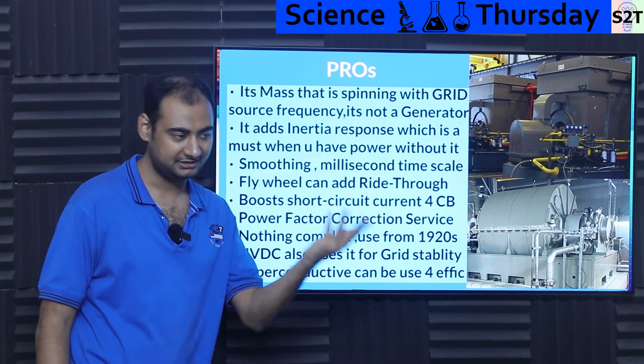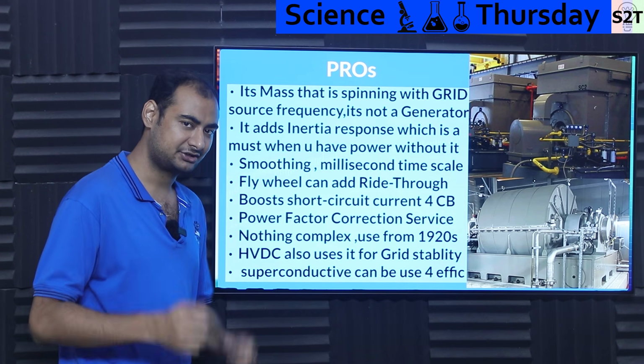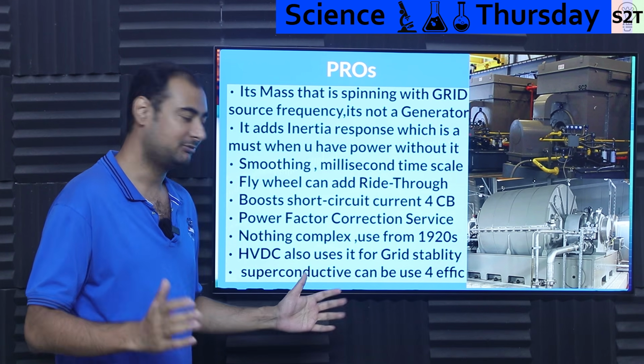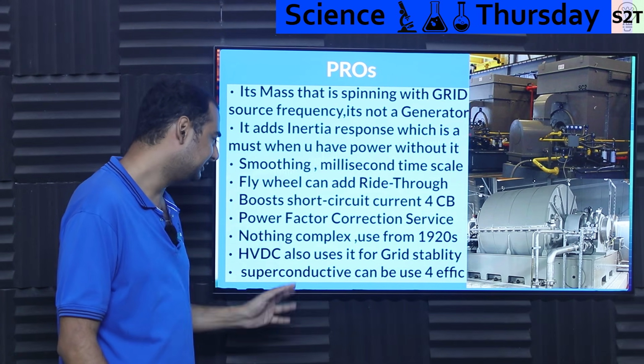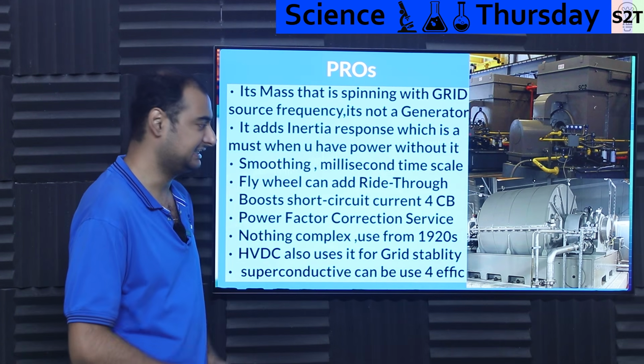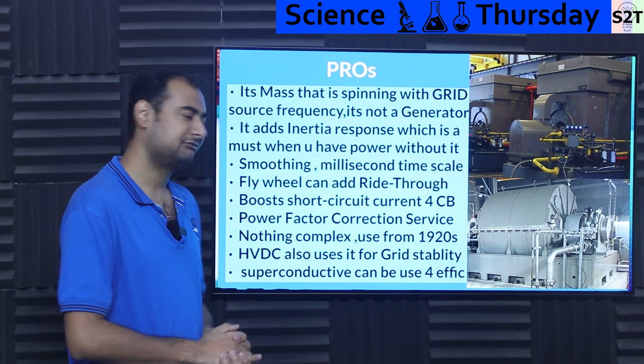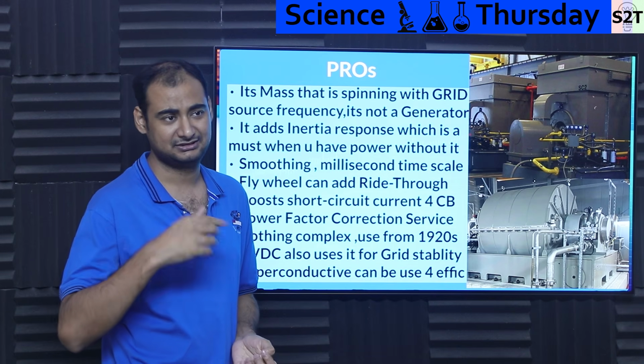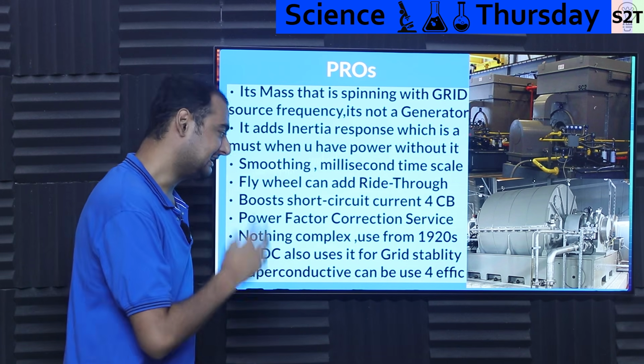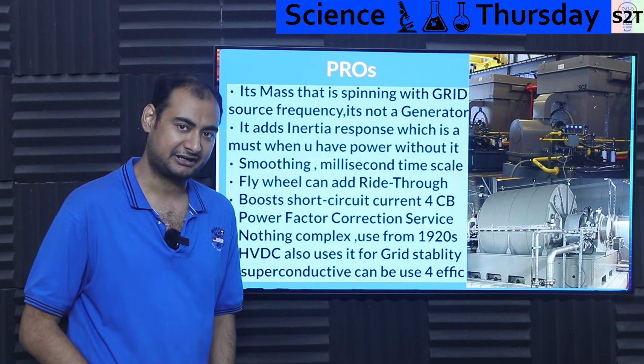And with power factor correction, you have rotor current control, power factor correction, the inverter becomes easier, and everybody's life becomes better. Fundamentally it's nothing complex, it's ancient technology. How ancient? From the 1920s we've been using it, and the synchronous motor itself is even more ancient. By the 1920s we started to utilize it for power factor correction.